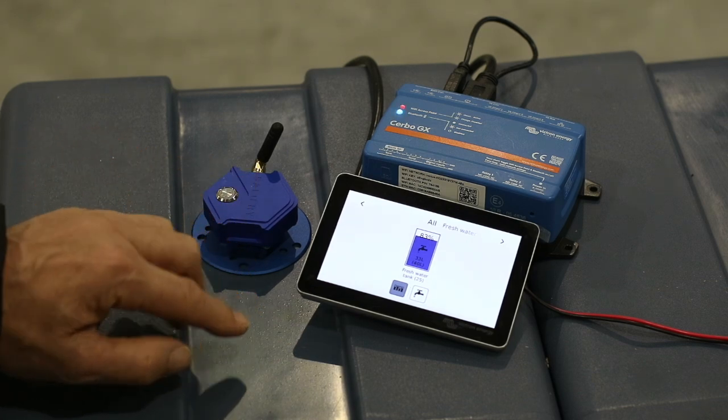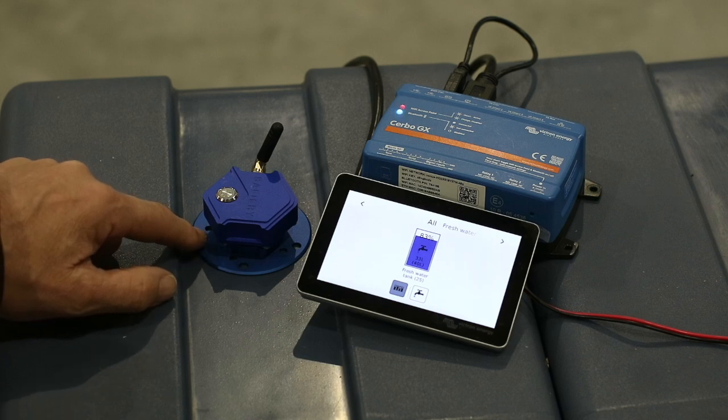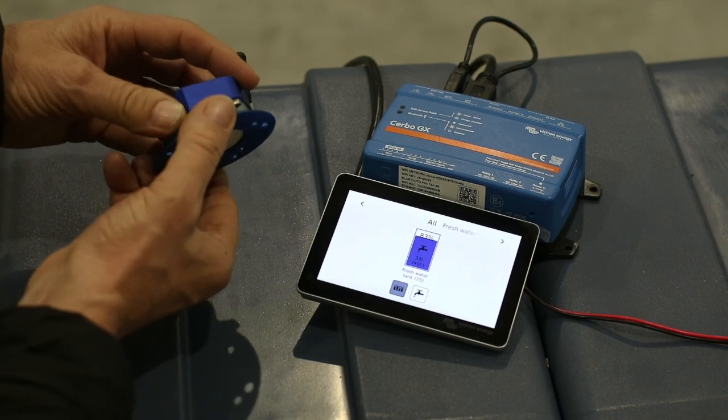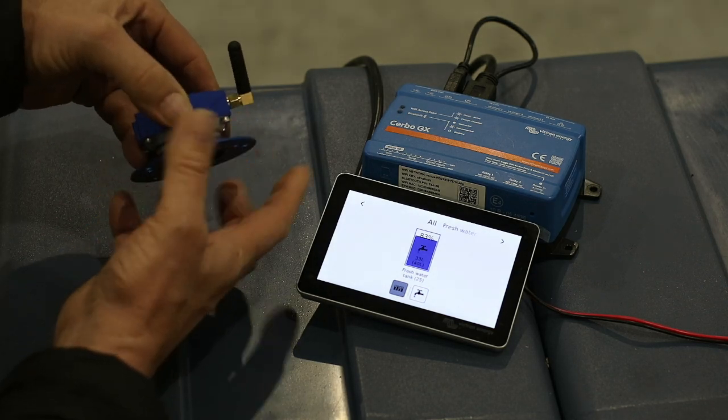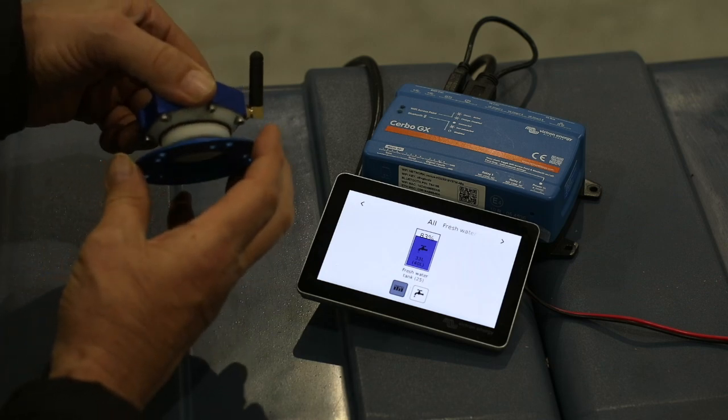For metal tanks, use the five-hole pattern that we've got at the bottom here. I'll just lift that up to show, and then by unscrewing this, you can remove it, change the battery inside. There's a seal on it that's got a Fresnel lens on it.